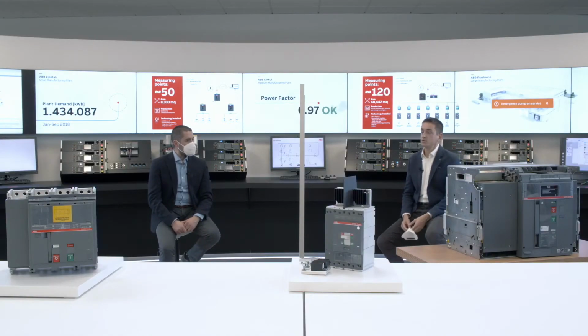Thank you, Riccardo and Nicola. We know that DC interruption has been very complex in the past. Can you explain how we solved this issue and what the several benefits of our DC solutions are? Yes, so DC current is not easy to break, and that's why for breakers we need to develop a specific solution internally and externally on every single breaker. Internally, for instance, we developed a specific arc chamber that helps to break DC current, especially at higher voltages. Externally, we need to connect poles in series to help the breaker do its job. And that's what we do with the connection in series of poles.